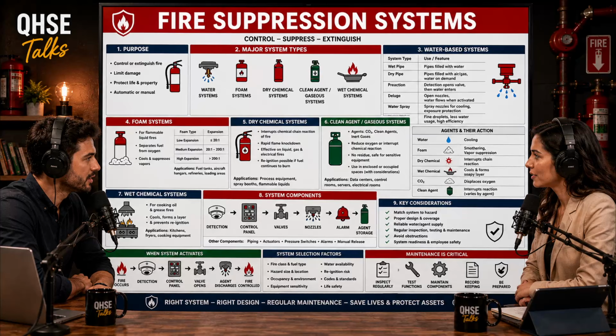A rigorous MOC review process ensures a safety engineer asks, is the existing wet pipe sprinkler system still adequate? And the answer would likely be no, because water on a solvent fire might spread it. Right. You might have to install a localized high-expansion foam system before you allow the new process to begin.